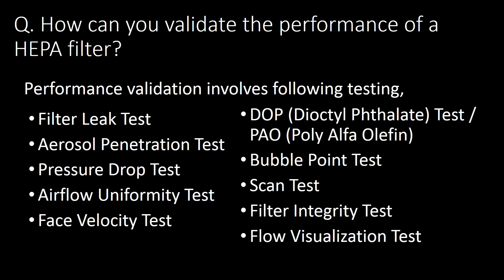How can you validate the performance of a HEPA filter? Performance validation involves the following tests: filter leak test, aerosol penetration test, pressure drop test, airflow uniformity test, face velocity test, DOP test (dioctyl phthalate test) or PAO test (poly-alpha olefin test), bubble point test, scan test, filter integrity test, and flow visualization test.